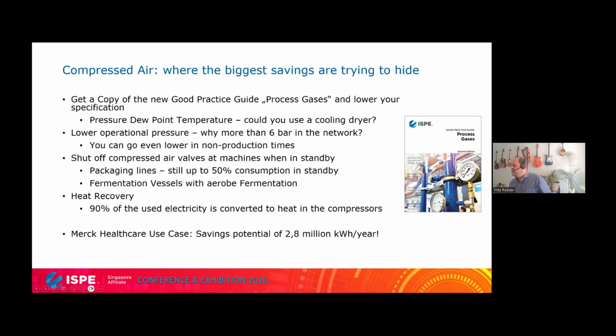You could even go to a +3 pressure dew point temperature at 6 bar or so operational pressure in compressed air. That would still be sufficient in most cases. It depends a bit, you're going to see later.